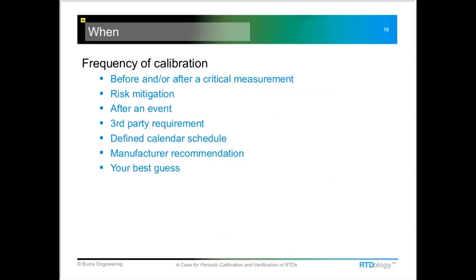Probably the toughest question I get is, well, how often do I need to calibrate? And this really boils down to your best guess. There are some parameters we can follow, some little checks we can do to help make that decision. There are processes where it may be a batch type setup, where we have a calibration or verification done to the temperature probe before the process is run, and then immediately afterwards, just to verify that it was measuring correctly throughout that whole batch process.